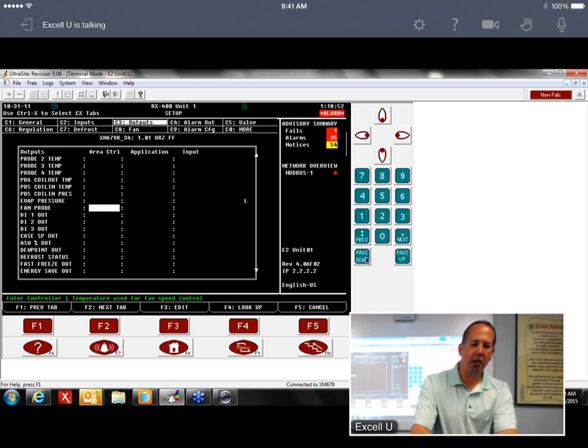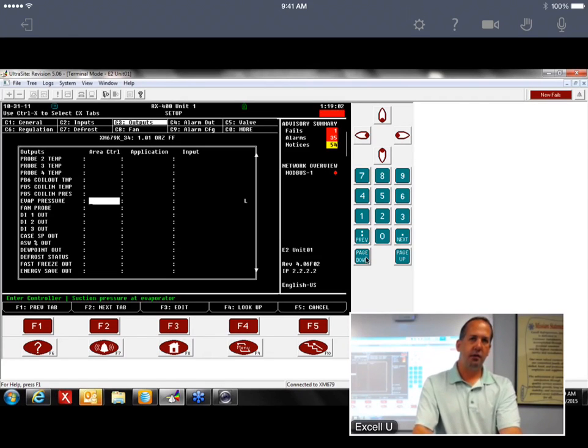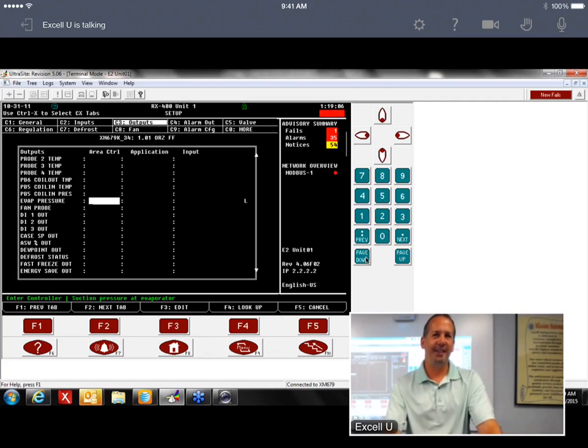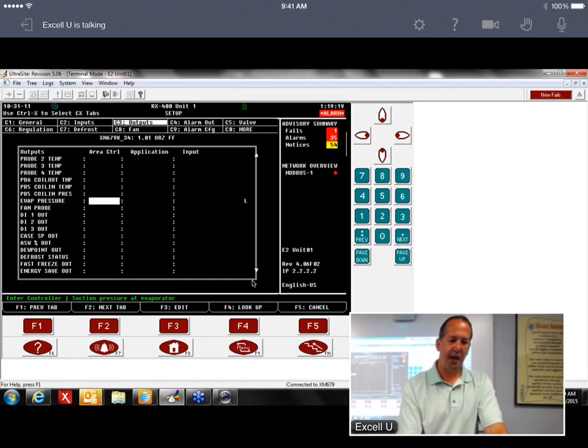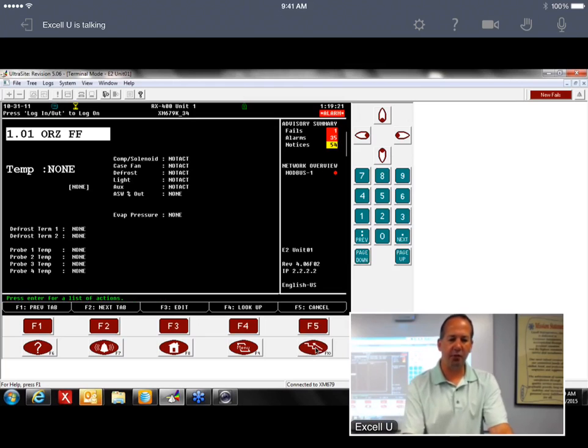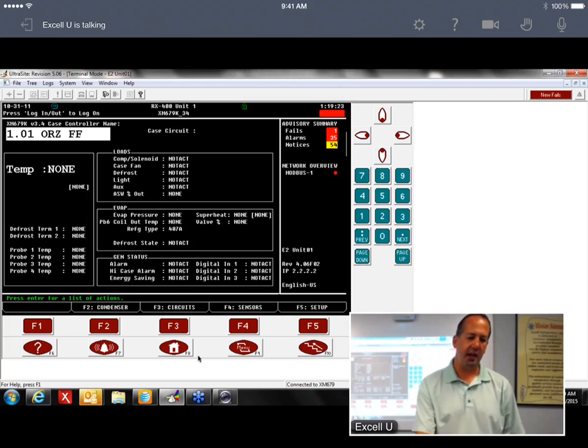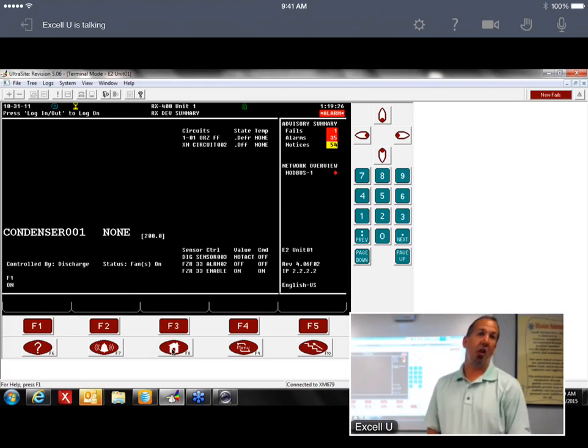So the only one that's not in the logging group is your coil out temp. And it must have been the old controller, because we were trying to log. Yeah, I think that controller was overloaded. It's at 99%. So Steve may have gone in and taken some stuff out of it because it was overloaded. But you can add them to the logging group. By default, most of them, with the exception of the coil out, are already in the logging group.